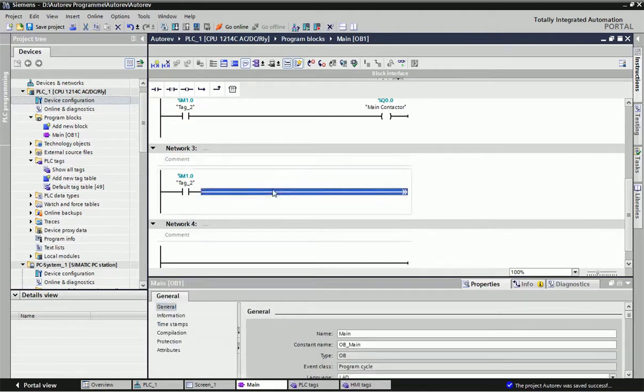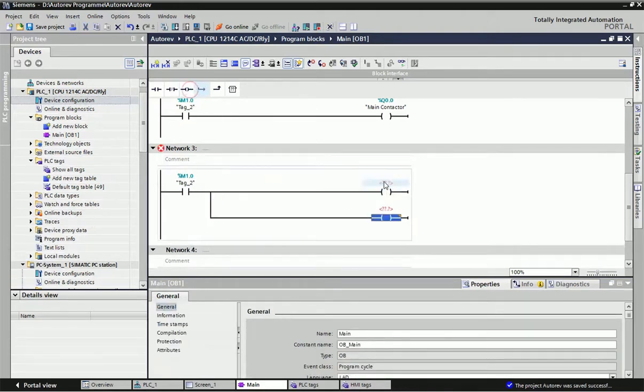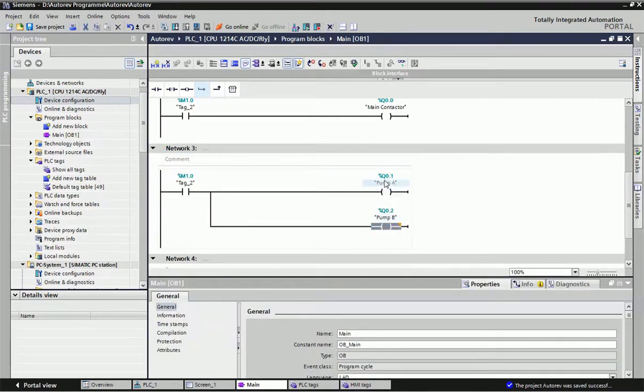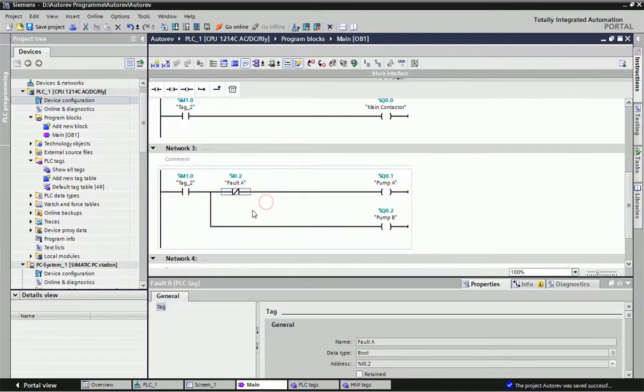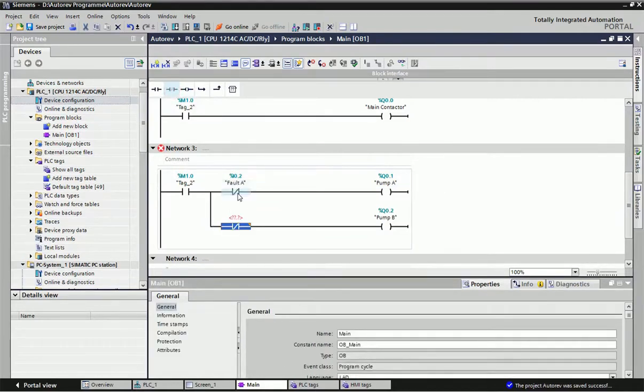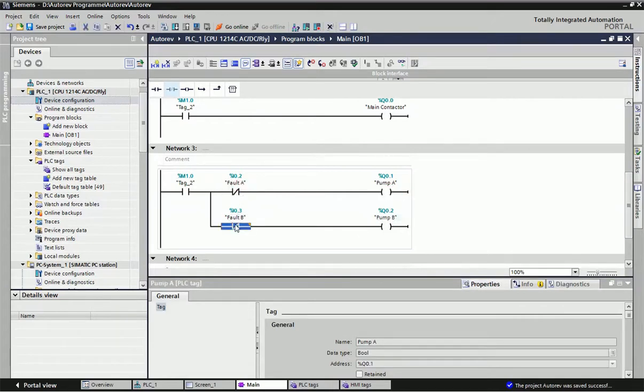From M1.0 you can start the main contactor using output Q0.0. I0.0 is the input and Q0.0 is the main contactor output. Then once again using memory bit M1.0, we can turn on pump A at output Q0.1 and pump B at output Q0.2. For simulating pump failure, I have added NC contacts — for example, fault input I0.2 for pump A — so when I create a fault, this NC contact opens and the pump turns off.